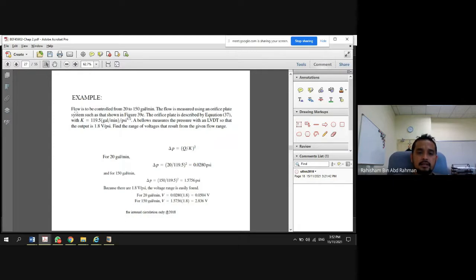Alright, again, okay, worked example. Flow rate can be controlled from 20 to 150 gallon per minute. Macam tadi, previously per second, now per minute. The flow is measured using the orifice plate system such as figure 39. Okay, assume the previous illustration. The orifice plate is described with K of 119.5 gallon per minute per PSI. Okay, sama. Then the pressure is measured with an LVDT. The sensitivity is 1.8 volt per PSI. Okay, find the range.